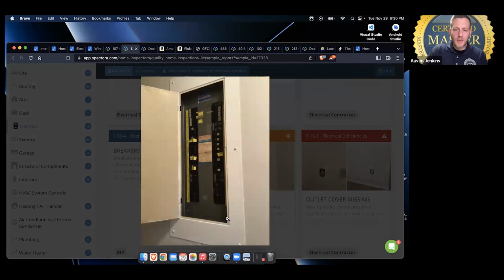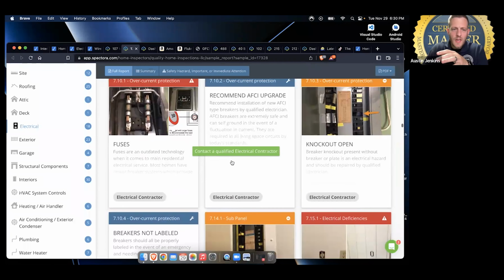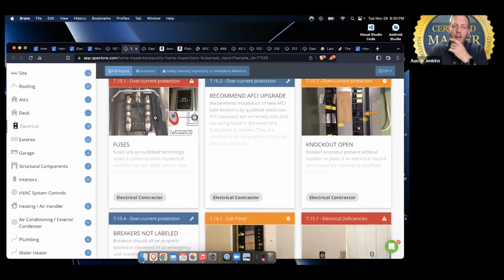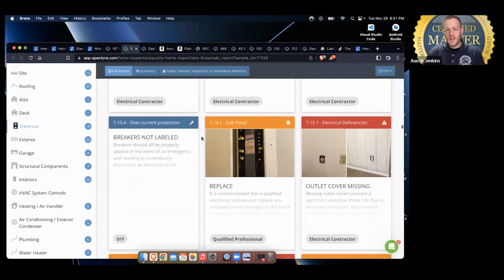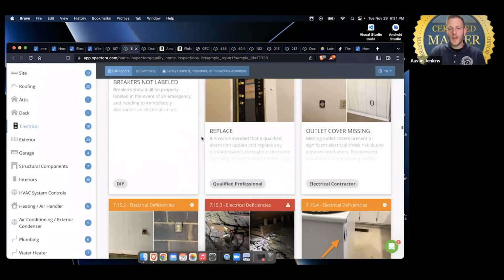I did recommend this panel be replaced simply because it had a lot of electrical deficiencies, and due to the age of the panel and the main disconnect with the fuses, I strongly recommended they be replaced. Anytime you come across fuses with today's electrical demand, it's okay to recommend replacement. I know a lot of electricians will say it's not needed, but again, your job is to protect your client and the house while protecting yourself.